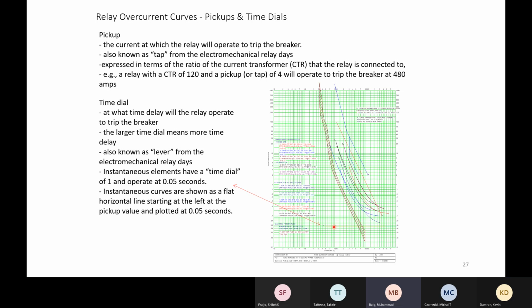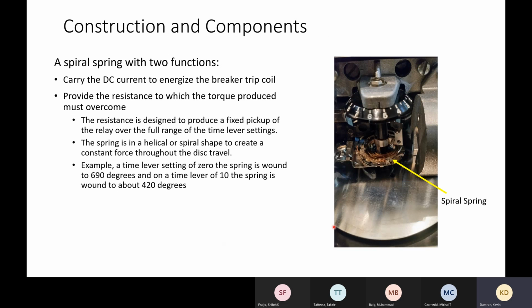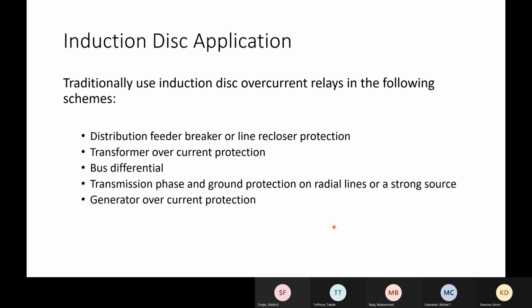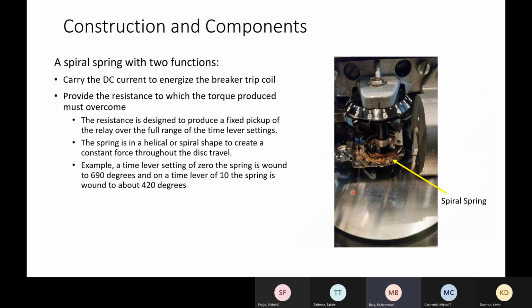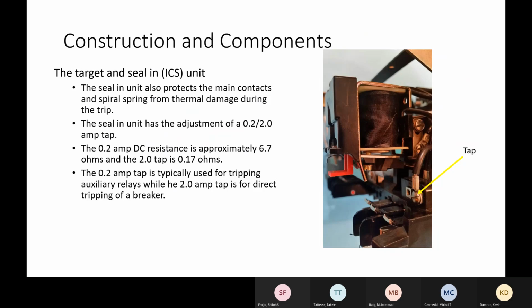So is it mostly preferred to use it only on the distribution part, not on the transmission, right? So you don't typically use, if we go back to that first slide, the only time you can use an overcurrent like this typically is for transmission if it's radial. Okay, so sounds good. A radial transmission line is the same as a distribution feeder, right? But generally most transmission is operated non-radial. Right, impedance. I got it. I think you answered my question. Thanks, Kevin. No problem.